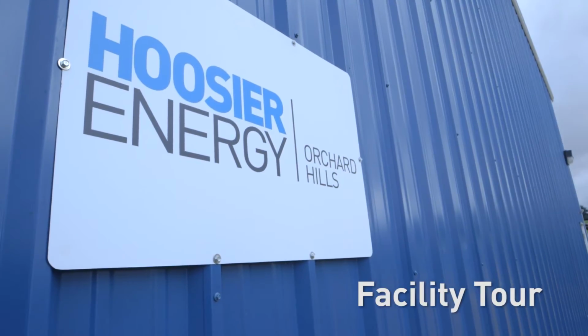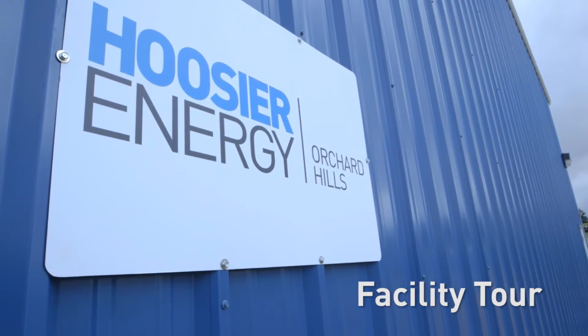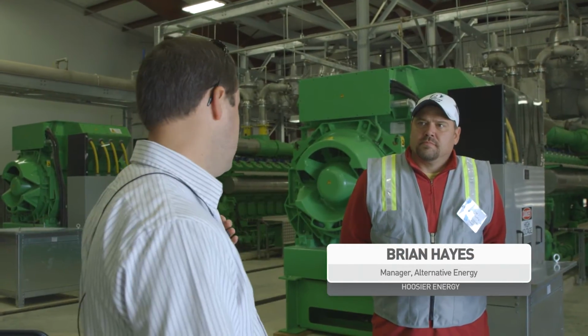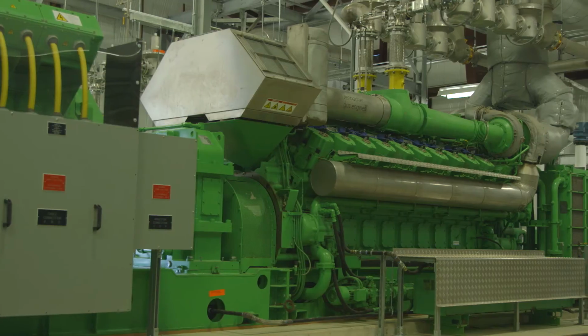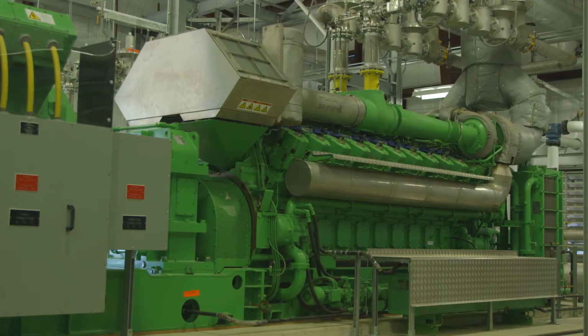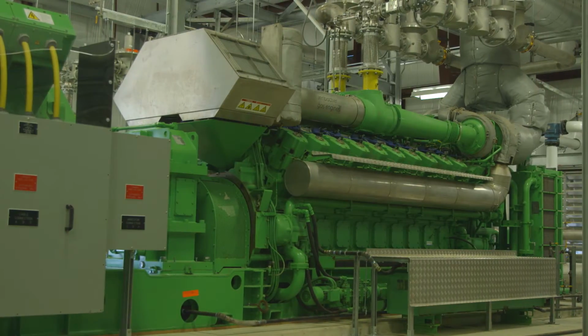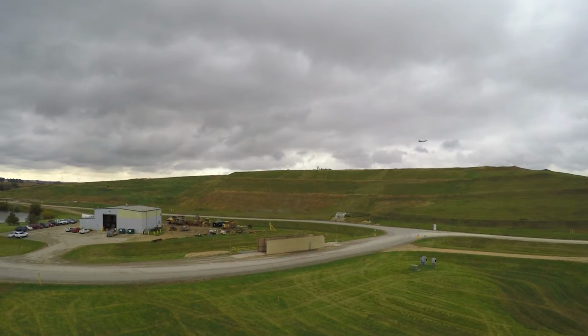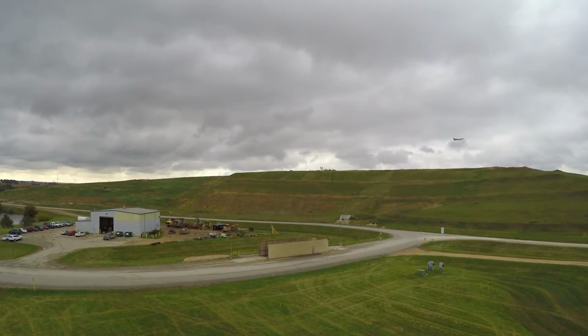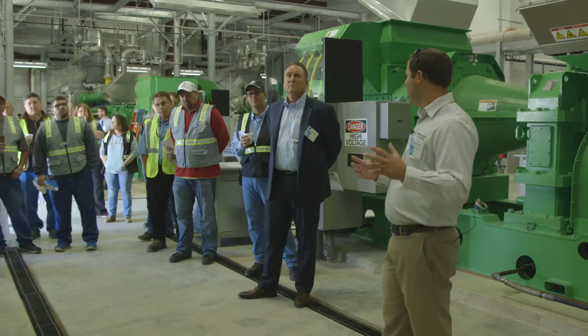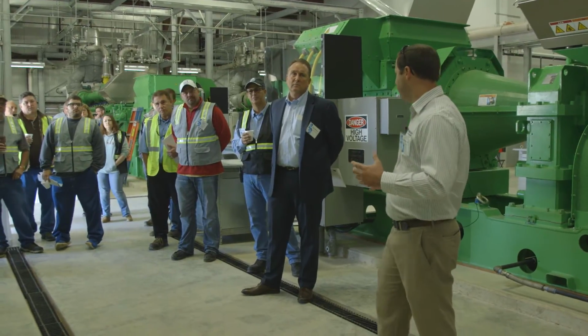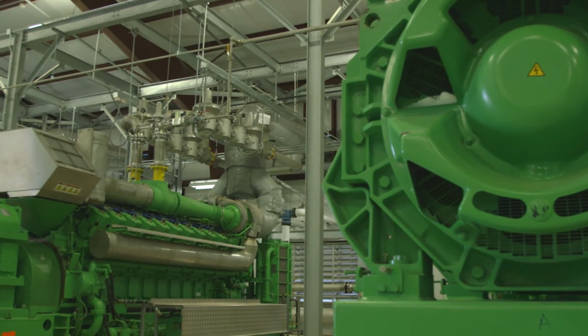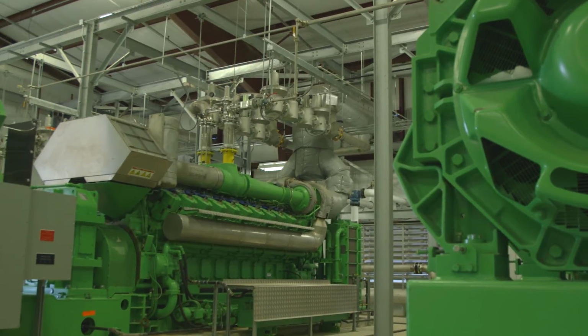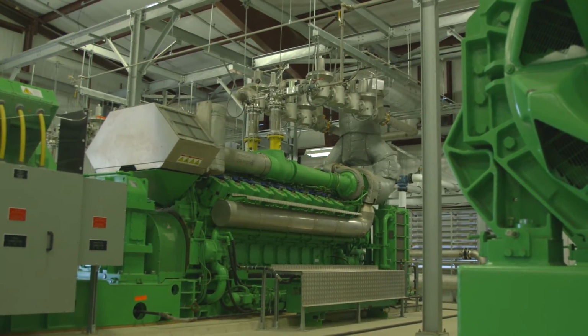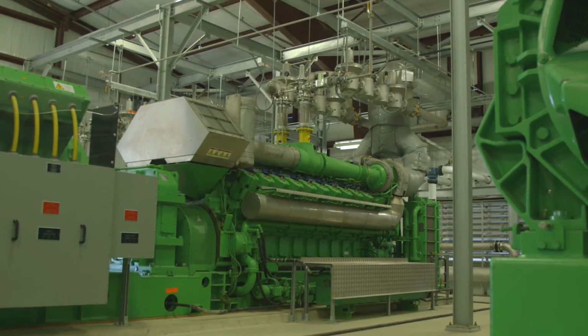We're pretty excited about the Orchard Hills generating station. We produce 16 megawatts of alternative energy at this site. We do it with these 6 GE Jenbacher 620 engines. Each engine itself produces approximately 2.8 megawatts of clean power. The landfill gas from the Advanced Disposal landfill actually comes in and burns in each of these engines. That combustion creates mechanical energy, which rotates our generators and produces that electric power that we generate at 4,160 volts. And then we send it onto the Commonwealth Edison grid.